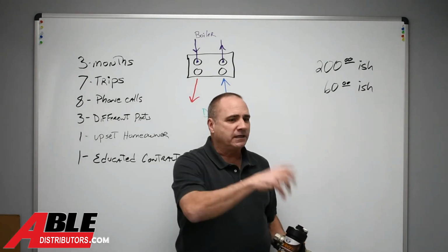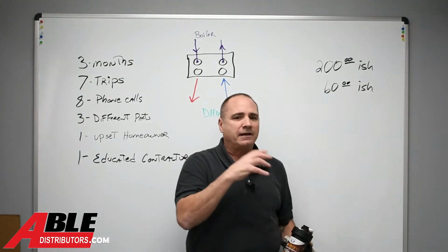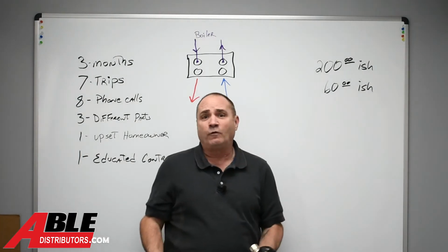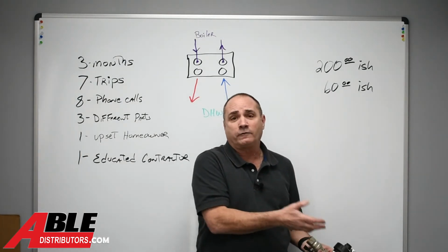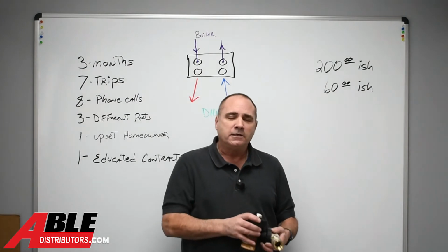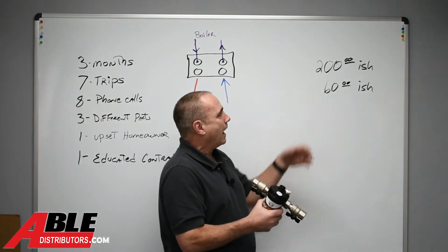But honestly, if it's that bad, you don't know what somebody put in that system. Did they put leak sealant in there? Did they put any additives in? Is this the 4th boiler and it's still the same water from 3 boilers ago? You just never know. To me, I would have done both.